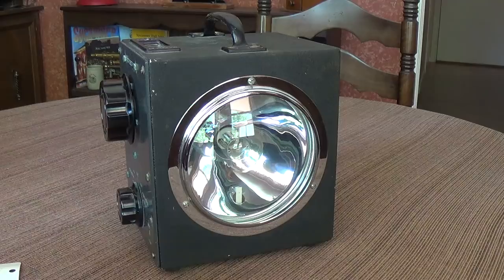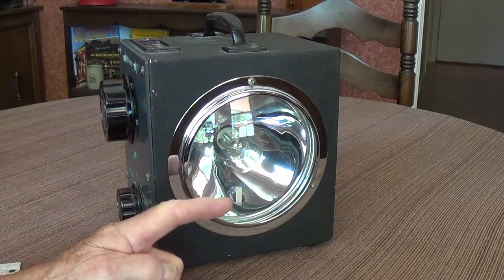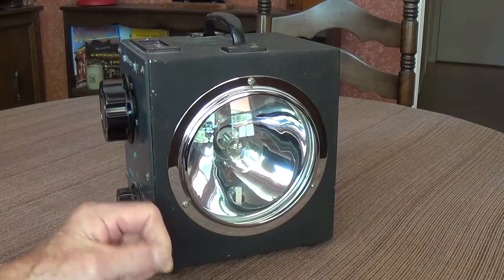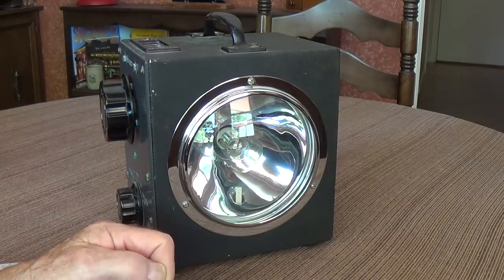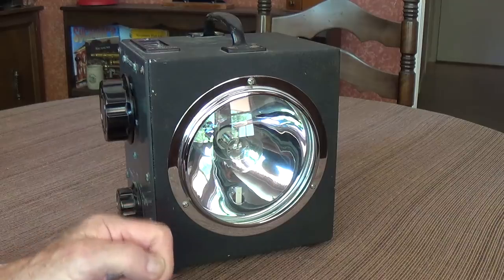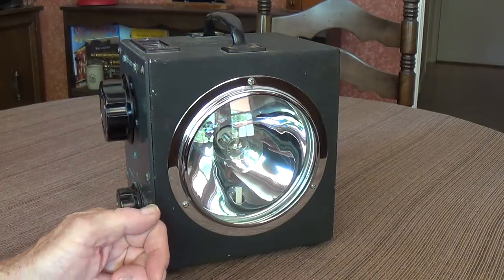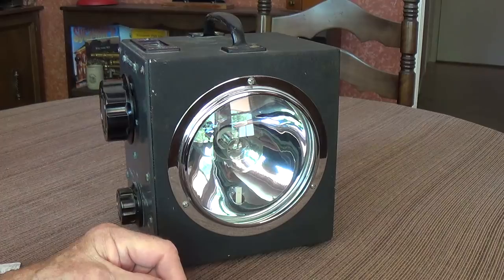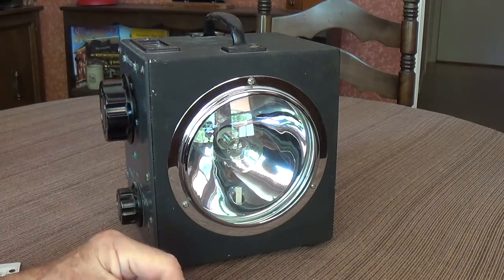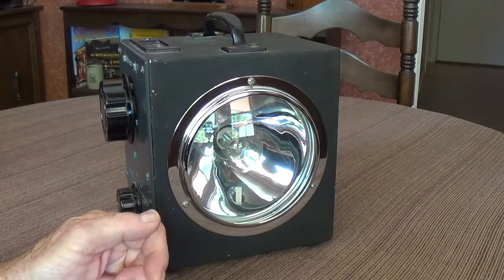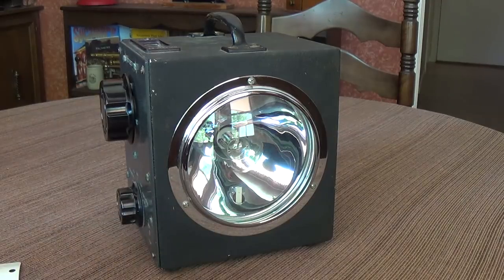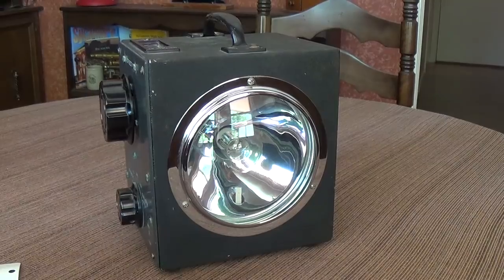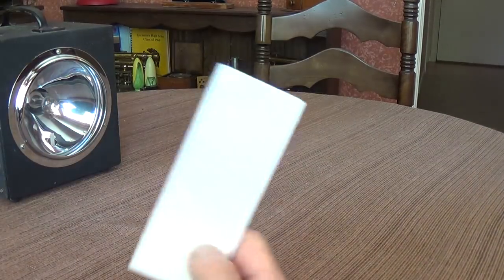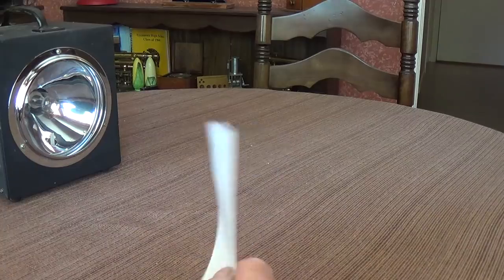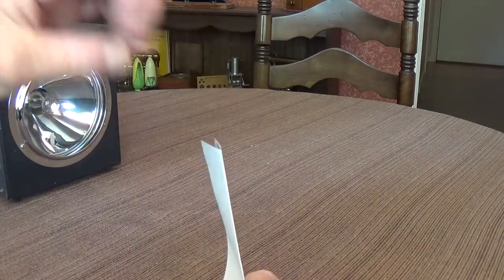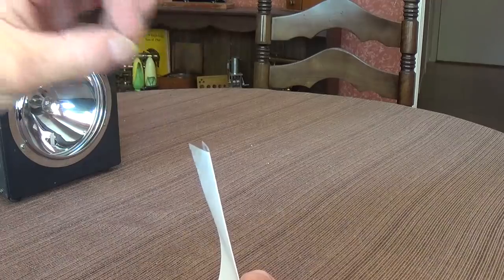The reason is that the leaf at 3600 vibrations per minute can be used to calibrate at any even fraction of that vibration rate. In other words, 1/2, it could calibrate to 1800. 1/4, it can calibrate to 900. 1/8, it would be good for 450 vibrations per minute. Now, let's explain why that's true. Okay, for this wonderful demo, this is going to be the little reed or leaf moving back and forth, and this is going to be the strobe flashing.